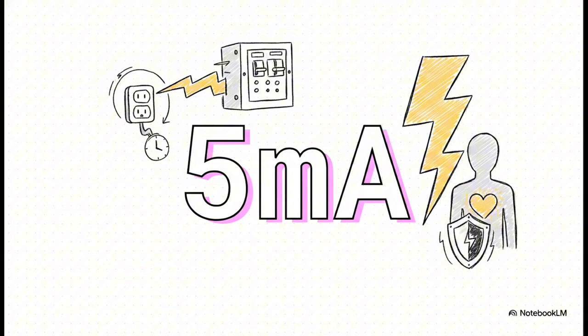To put that into perspective, a standard circuit breaker might not even trip until it hits 15 or 20 amps. That's literally thousands of times higher. When a GFCI detects that tiny 5 milliamp difference, it breaks the circuit in a fraction of a second. We're talking around 1/40th of a second. This drastically reduces the severity of a shock, preventing the current from fatally disrupting the heart.